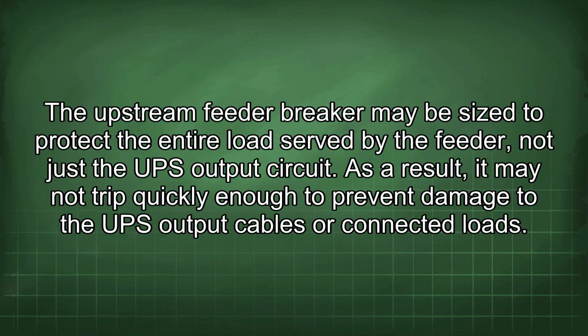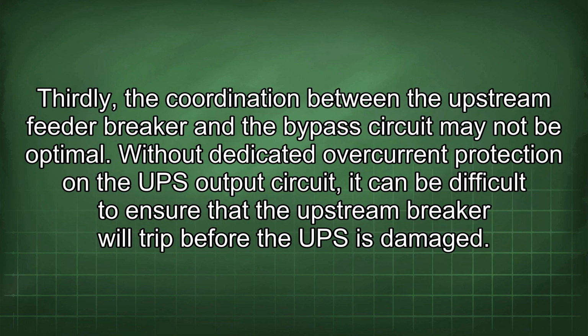The upstream feeder breaker may be sized to protect the entire load served by the feeder, not just the UPS output circuit. As a result, it may not trip quickly enough to prevent damage to the UPS output cables or connected loads. Thirdly, the coordination between the upstream feeder breaker and the bypass circuit may not be optimal. Without dedicated overcurrent protection on the UPS output circuit, it can be difficult to ensure that the upstream breaker will trip before the UPS is damaged.